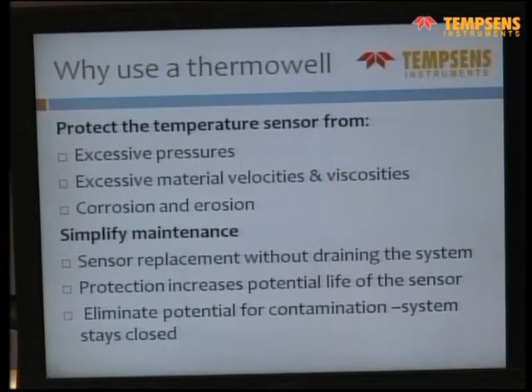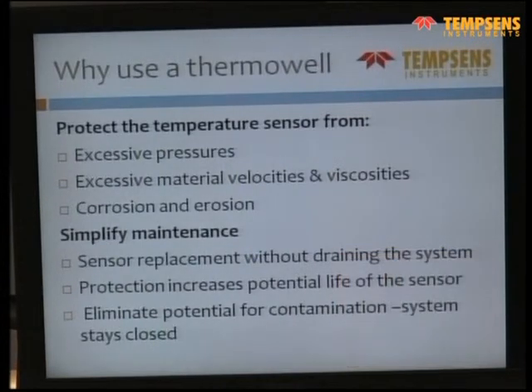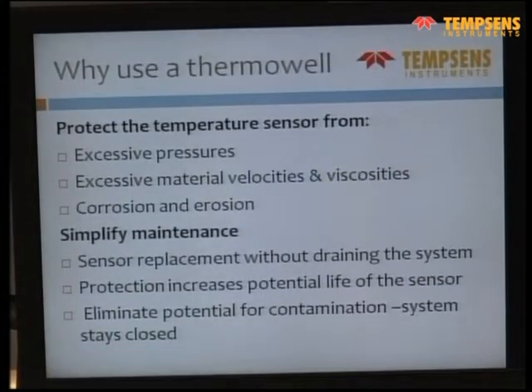One is to protect the temperature sensor from excessive pressure, from excessive material velocities, and protect it from corrosion and erosion. The second important reason for using a thermowell is easier maintenance. In case you take out the sensor, the thermowell is still in the process, so you don't have to stop the process and you can change the sensor. Then you would increase the life of the sensor. And third, you eliminate the possibility of contamination.